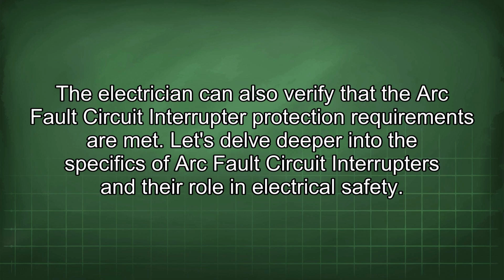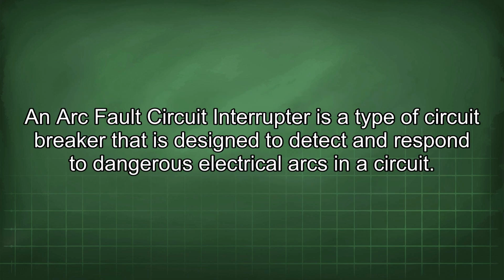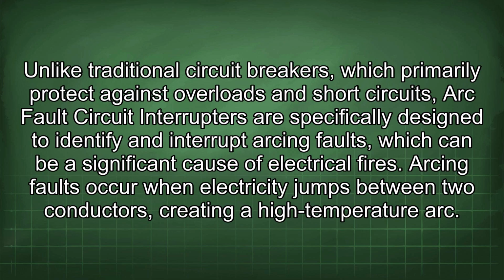Let's delve deeper into the specifics of arc fault circuit interrupters and their role in electrical safety. An arc fault circuit interrupter is a type of circuit breaker that is designed to detect and respond to dangerous electrical arcs in a circuit. Unlike traditional circuit breakers, which primarily protect against overloads and short circuits, arc fault circuit interrupters are specifically designed to identify and interrupt arcing faults, which can be a significant cause of electrical fires.